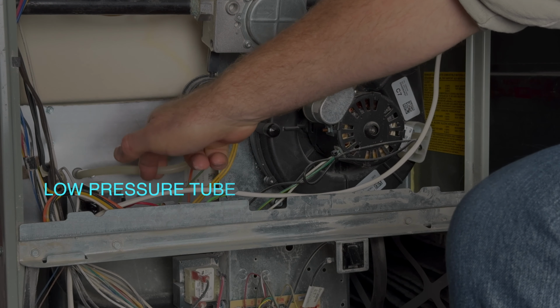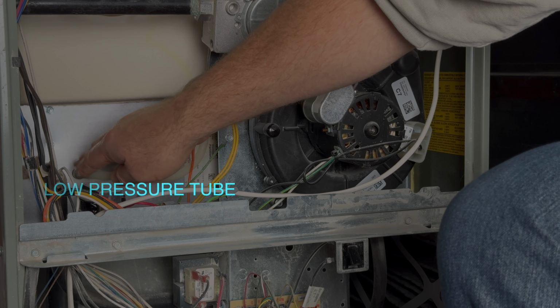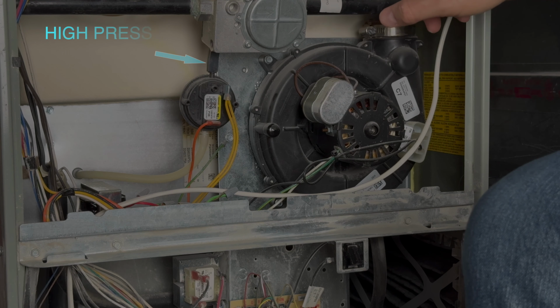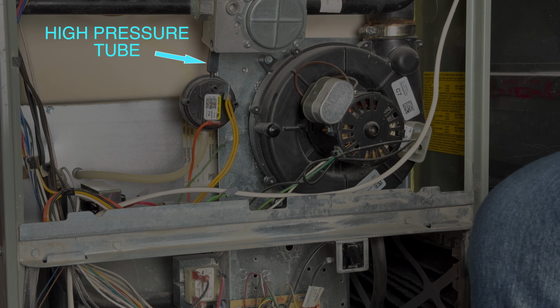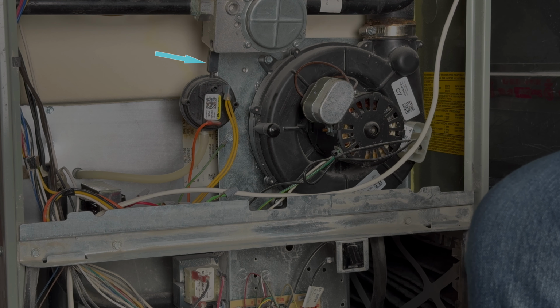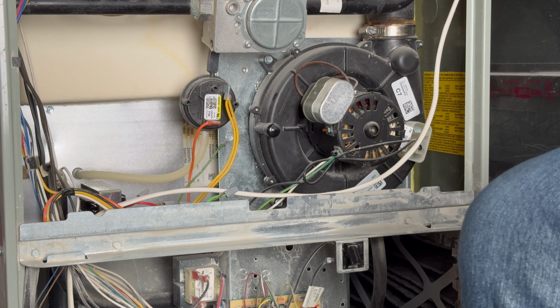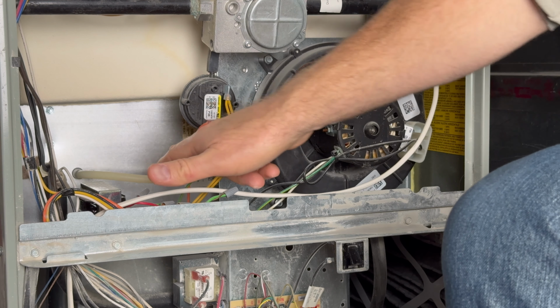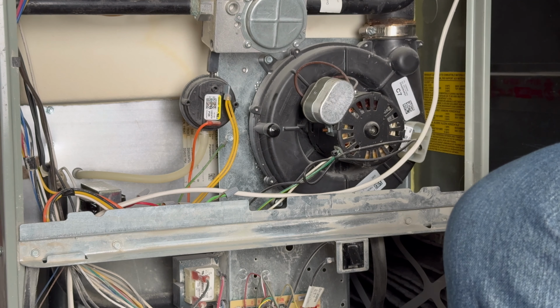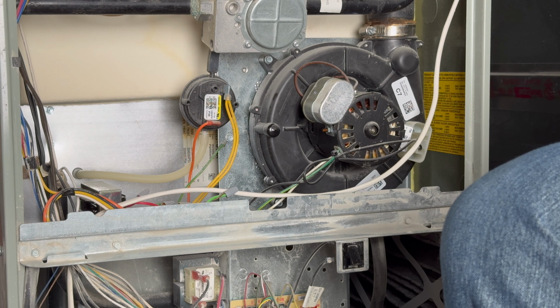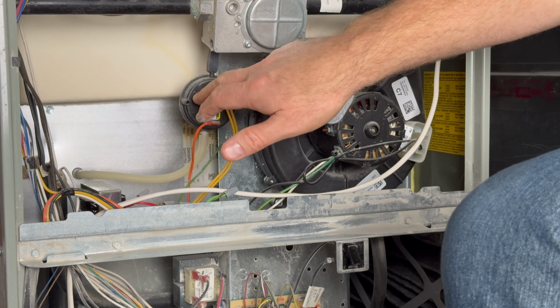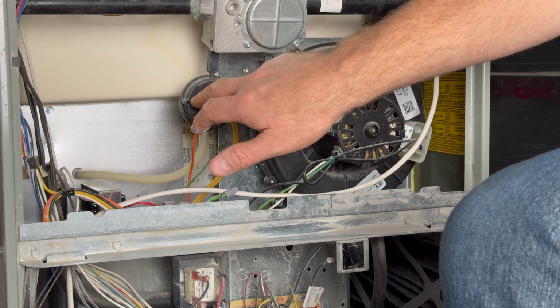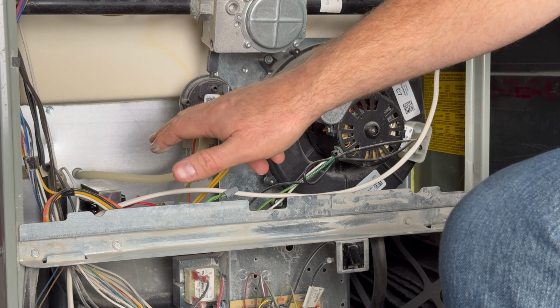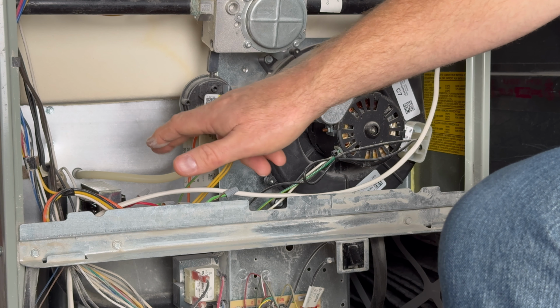Now this tube is the low pressure or suction side of our exhaust fan. And this tube up here is the high pressure tube, which is connected to the discharge side of the combustion exhaust fan. This pressure switch compares the low pressure suction to the high pressure discharge sides of the fan and has to have a differential pressure of at least 1.65 inches of water column to pull in a diaphragm, which then allows the normally open electrical microswitch to close, completing the run safety circuit.